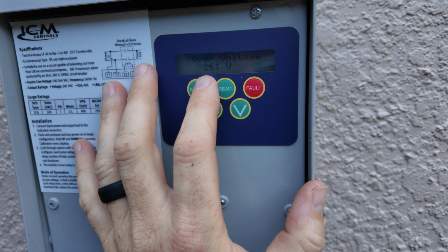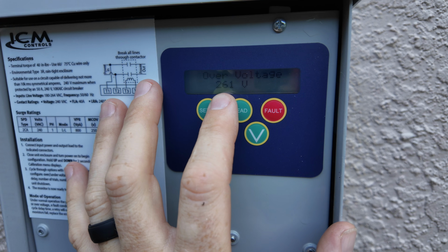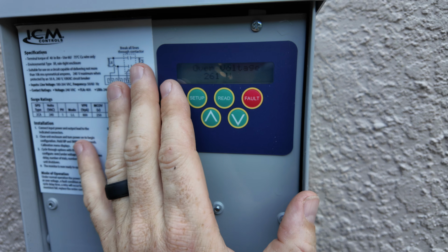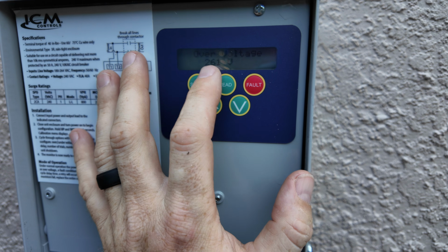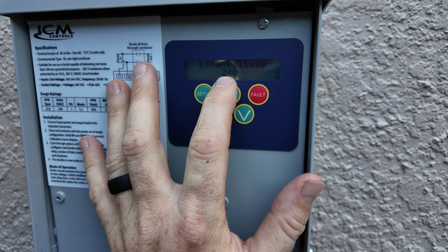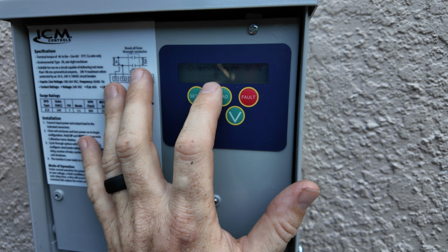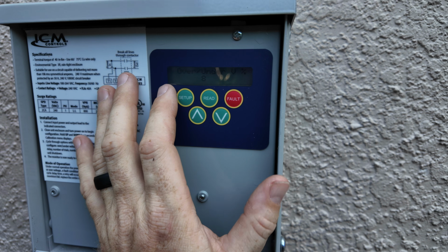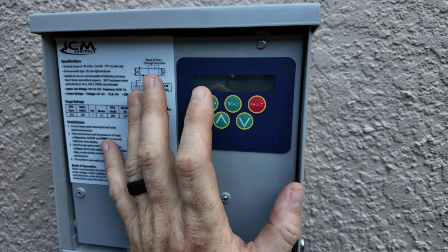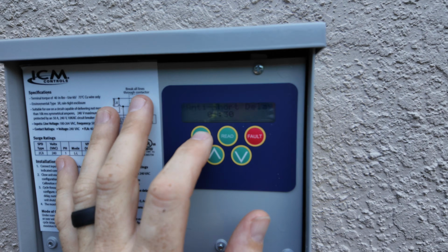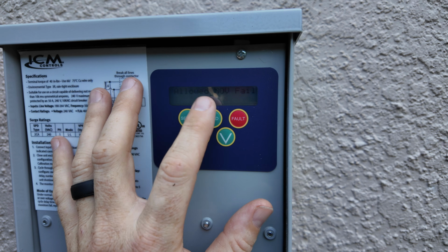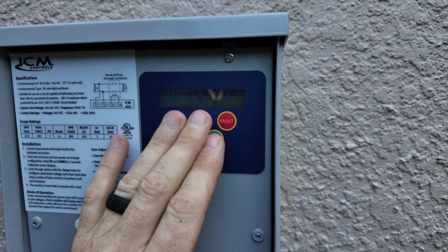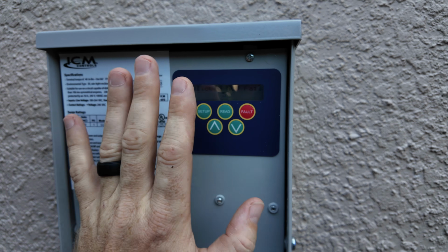All right, so we're gonna go in here and look. See, we had an over voltage of 261, okay? So what that basically means is this thing is set up for 240 volts, okay? We have an 8% on that, okay? I'd like to maybe do 10 or 5, but the power in this space is definitely going to be above 250 for the most part. So we've got to try to let this thing at least run without it being a problem. So we have it at that 8% for them. 90-second delay, auto reset, and it's got 5 MOVs. We set it at 5, that's what the customer wanted, but that's how many come in this.